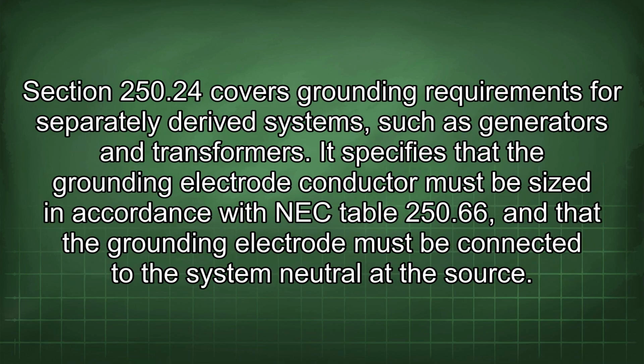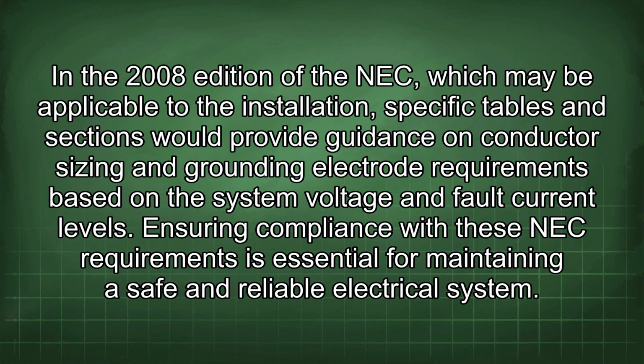Section 250.24 covers grounding requirements for separately derived systems such as generators and transformers. It specifies that the grounding electrode conductor must be sized in accordance with NEC Table 250.66, and that the grounding electrode must be connected to the system neutral at the source. In the 2008 edition of the NEC, which may be applicable to the installation, specific tables and sections would provide guidance on conductor sizing and grounding electrode requirements based on the system voltage and fault current levels. Ensuring compliance with these NEC requirements is essential for maintaining a safe and reliable electrical system.